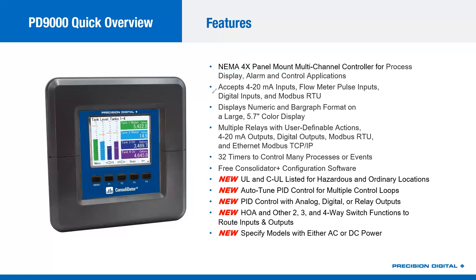It accepts 4 to 20 milliamp inputs, flow meter pulse inputs, digital inputs, and it is a Modbus device that can be a master, slave, or snooper. It has a great-looking display, with lots of relay, analog, and digital output possibilities. Ethernet for Modbus TCP/IP capabilities is great for integrating into an existing SCADA system. All sorts of timer capabilities are included — for example, to time how long a loading process takes or how long an alarm is on — and all of that is programmed via free Consolidator Plus configuration software.